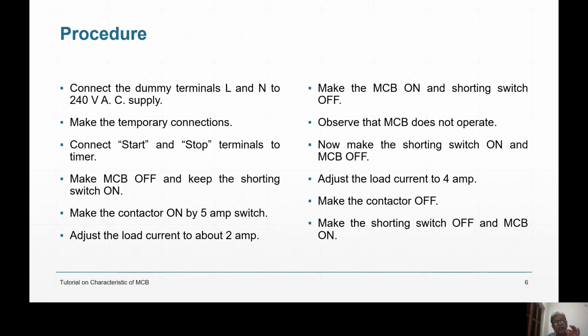Overload current is the same. I am passing 4 ampere in both cases. In one case 4 ampere from 0, but in another case 4 ampere from 2 ampere. So all MCBs invariably have two characteristics, and they are known as thermal withstand characteristics. That if so much current is passed for so much time, then the insulation will be damaged. So the characteristics are two, a double characteristic. One is hot, another is cold. Hot characteristic is always below cold characteristic. So one has to remember this when one is using an MCB. This is very important, right?